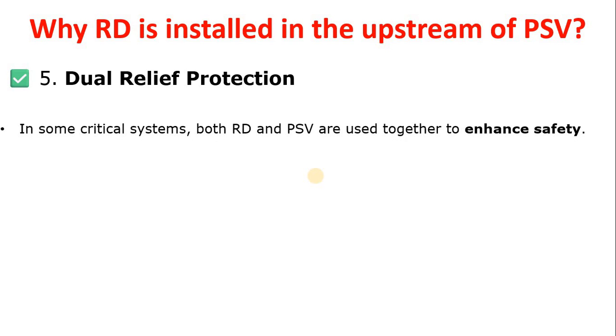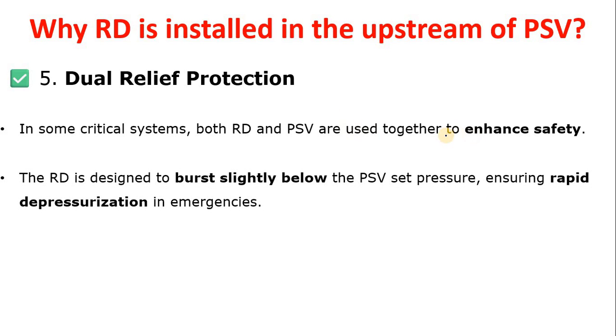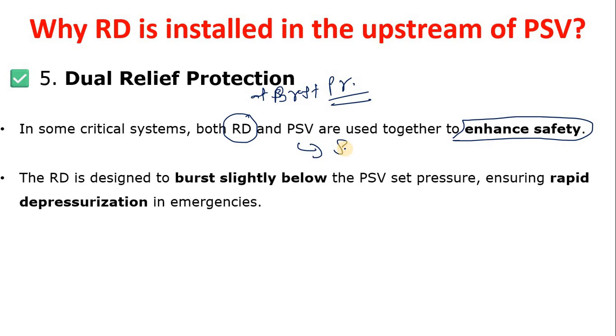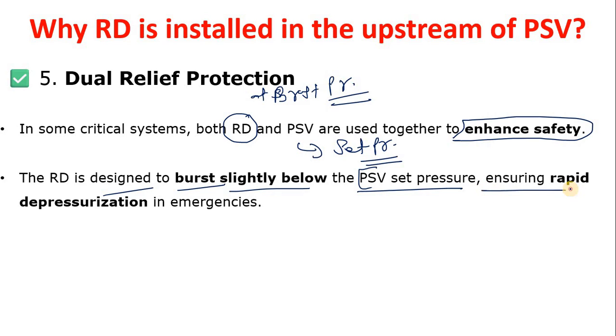Using both an RD and a PSV also provides dual relief protection. Since both are relief systems, using them together enhances safety. The RD is designed to burst at or slightly below the PSV set pressure, so that when the RD bursts you are alerted and the PSV can then open due to the pressure build-up. This ensures rapid depressurization in emergencies.